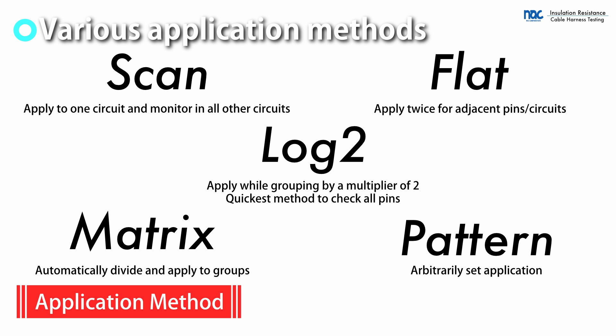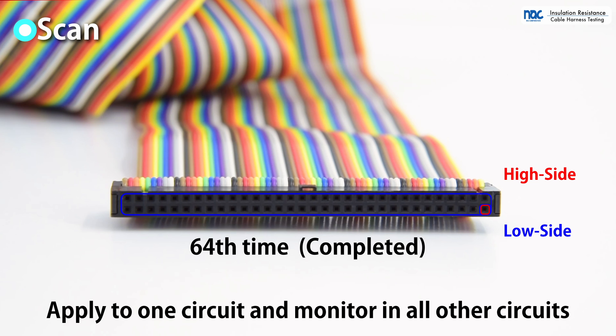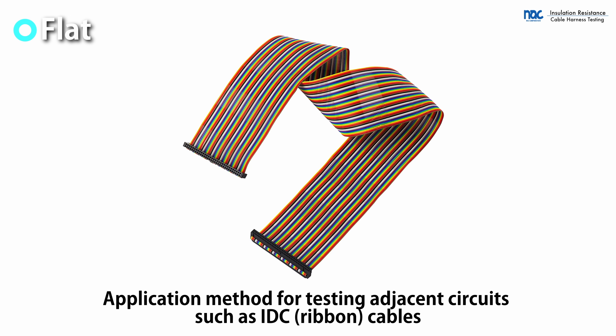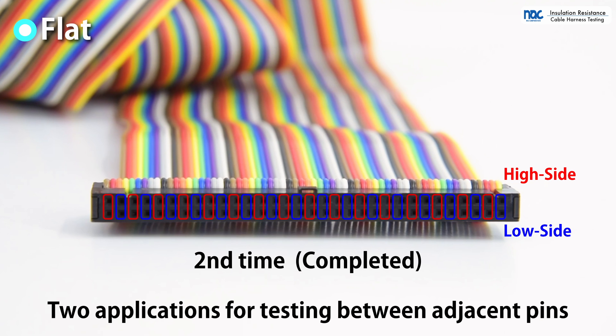There are several application methods. With scan, voltage is applied to one pin at a time while all other pins are monitored. High voltage is applied to all pins in sequence. This is equivalent to testing by an insulation tester. Flat is for testing ribbon cables. It is intended for testing adjacent pins and is completed in two applications.